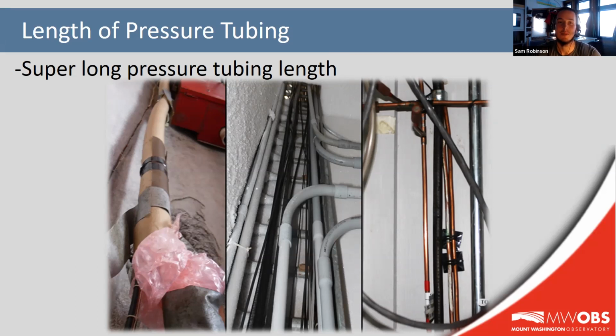It was theorized by Mount Washington Observatory employees back in 2013 that this very long length of tubing leads to dampening of pressure waves, which then leads to a loss of accuracy in the wind speed measurement. Basically, the pressure could be different at the transducer or sensor than it is up at the actual anemometer itself. So along with possible dampening of pressure waves due to this excessive tubing length, changes in air density due to the changes in temperature is also a theorized issue.